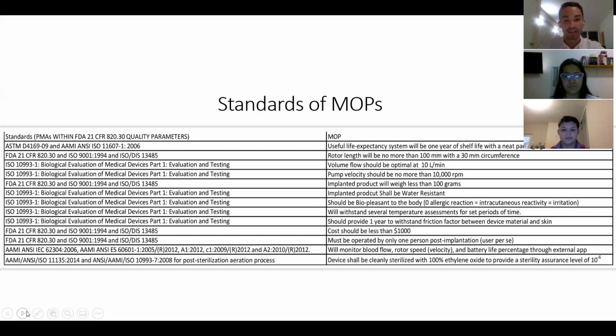There are many other agencies that are used for these specific MOPs, such as the American Society for Testing Materials, the American National Standards Institute, the Association for the Advancement of Medical Instrumentation, also called AAMI, and even the International Standardization Organization. For example, these are used for MOPs very necessary for the useful life expectancy of the system, which will be a 1-year shelf life, as well as different dimensions for the device design, such as rotor length, which will be no more than 100 millimeters, with a 30 millimeter circumference, or even volume flow, which is optimal at 10 liters per minute.